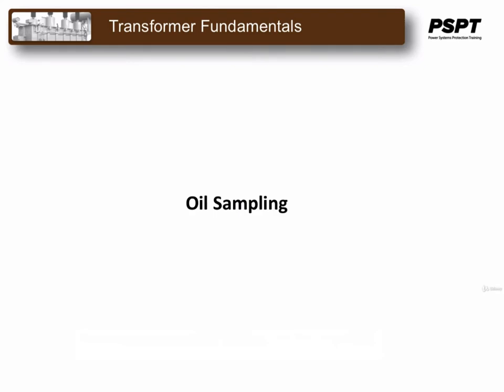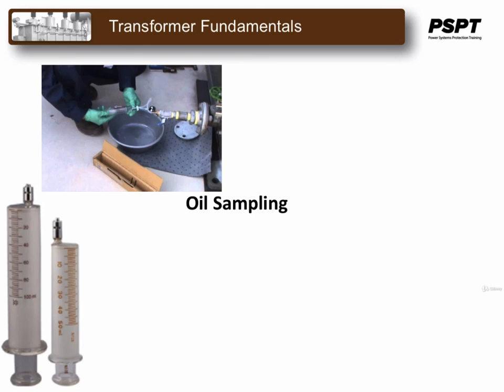Insulating oil analysis provides an early warning sign of a problem condition and is dependent on the quality of the oil sample that is sent to the lab. A sampling point on any equipment should be identified and clearly labeled. The same location should be used each time a sample is collected to ensure representative conditions are tested. This point should be located in a place where a live oil sample is active rather than in an area where the oil is static.